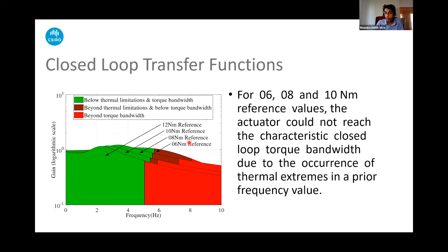Here in the bright red color, we can see we have plotted if the actuator reached the torque bandwidth before any thermal limitations. But for these three curves, which are 6, 8, and 10 Newton meter reference values, the actuator could not reach the characteristic closed loop torque bandwidth due to the occurrences of thermal extremes at prior frequency values, as those are shown in this dark red color from these three figures. So there we can see a problem. The thermal limitations are affecting the torque bandwidth.